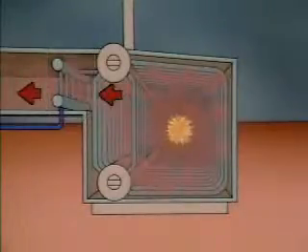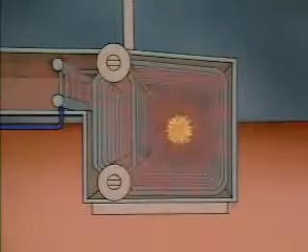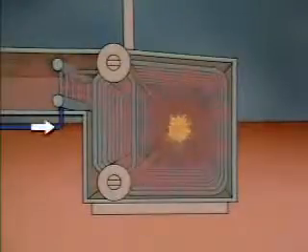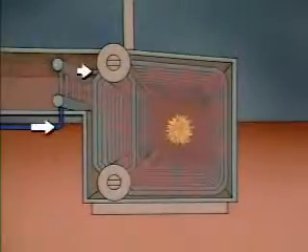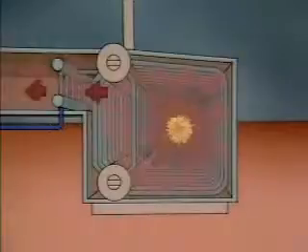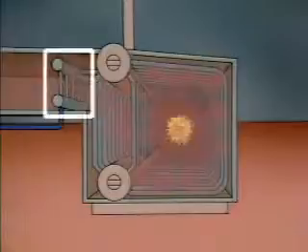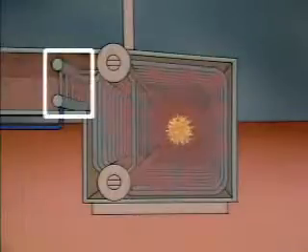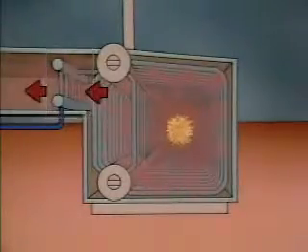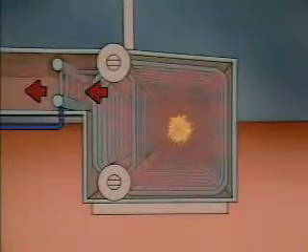Feed water is routed through the economizer tubes on its way to the steam drum and is heated by the hot combustion gases flowing past the tubes. The economizer improves boiler efficiency by making use of heat in the combustion gases that would otherwise be wasted.